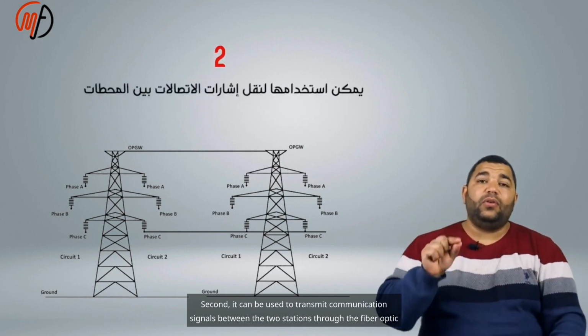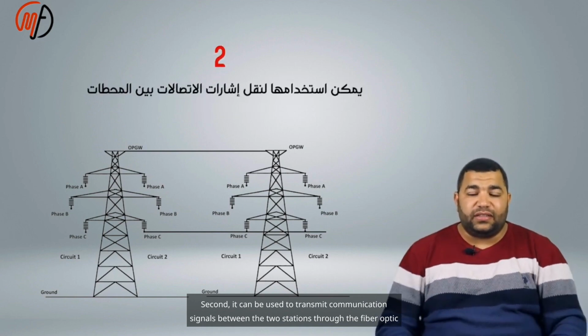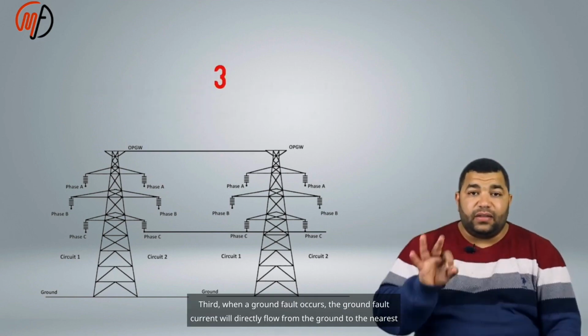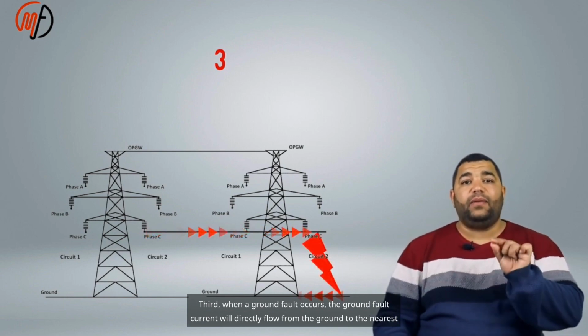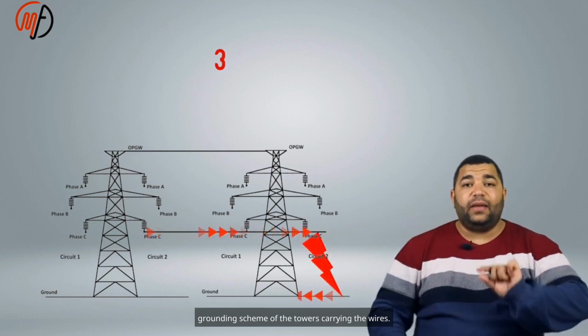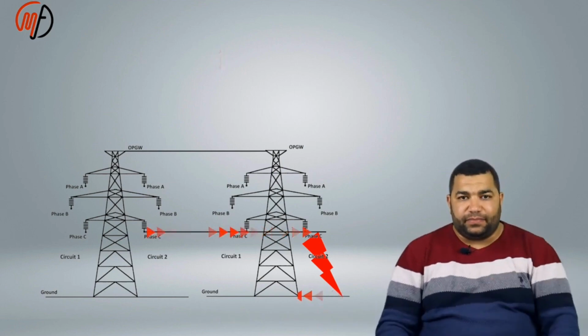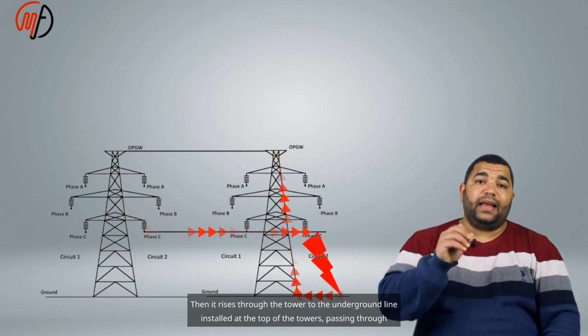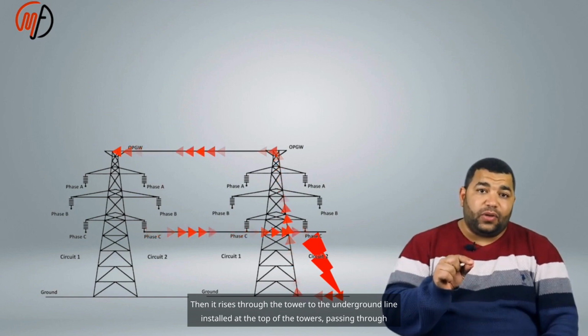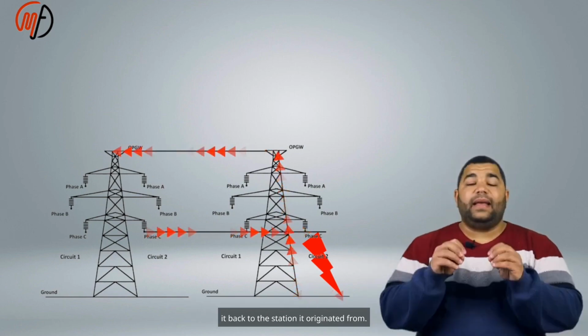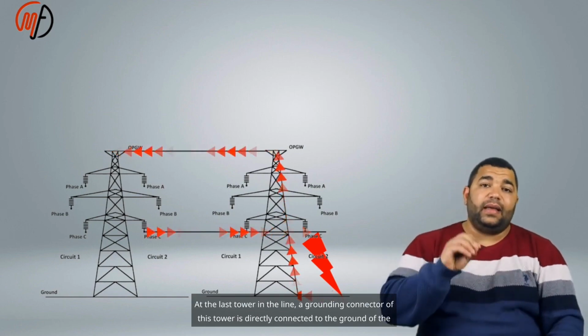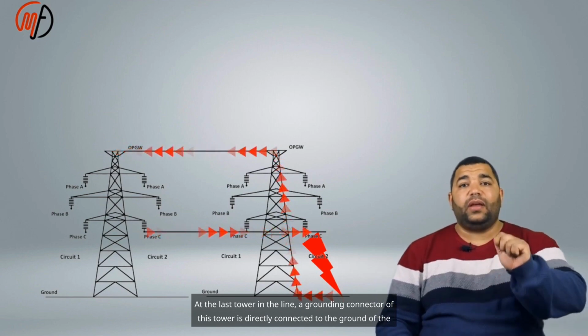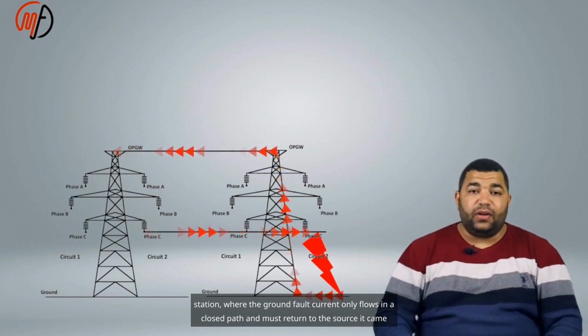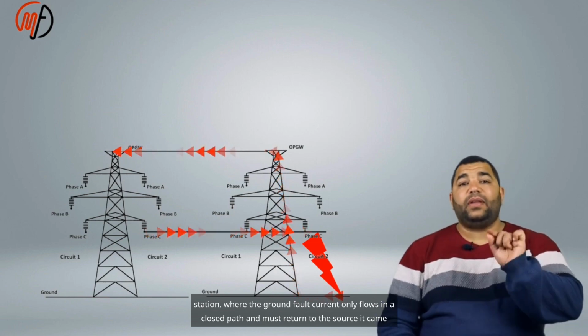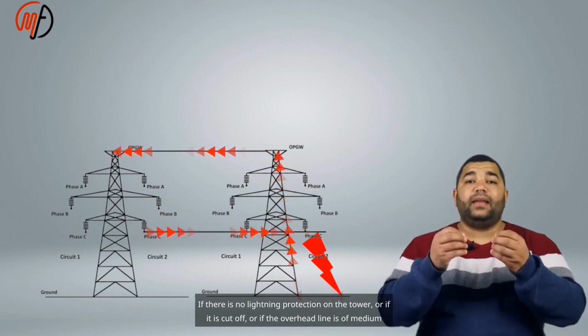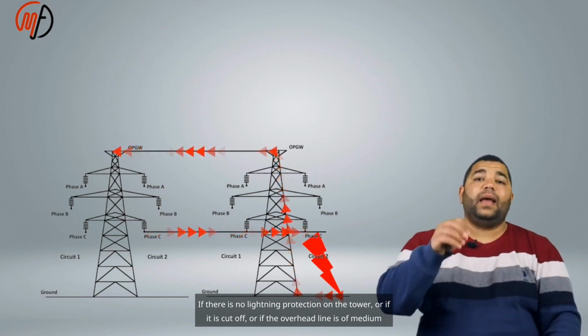Second, it can be used to transmit communication signals between the 2 stations through the fiber optic located in the middle. Third, when a ground fault occurs, the ground fault current will directly flow from the ground to the nearest grounding scheme of the towers carrying the wires. Then it rises through the tower to the overhead line installed at the top of the towers, passing through it back to the station it originated from. At the last tower in the line, a grounding connector of this tower is directly connected to the ground of the station, where the ground fault current only flows in a closed path and must return to the source it came from.